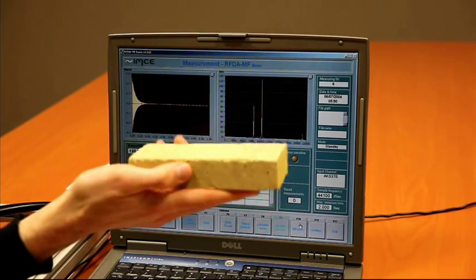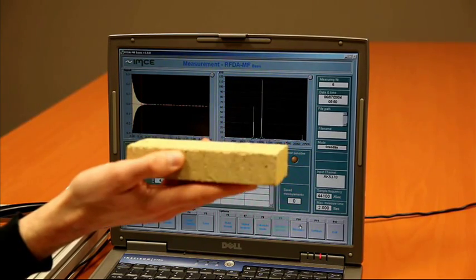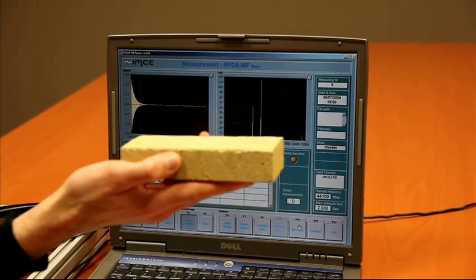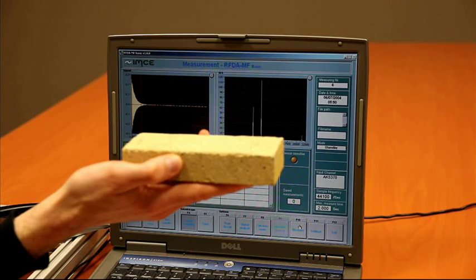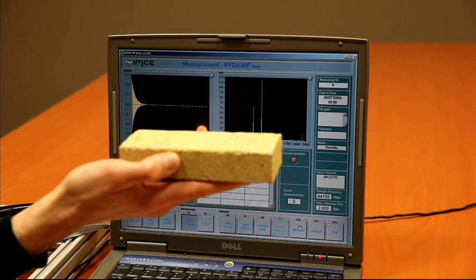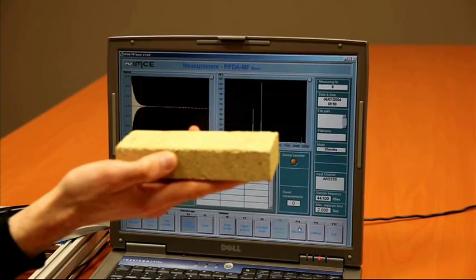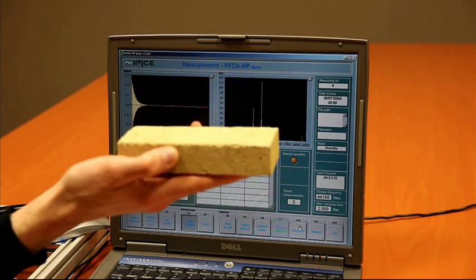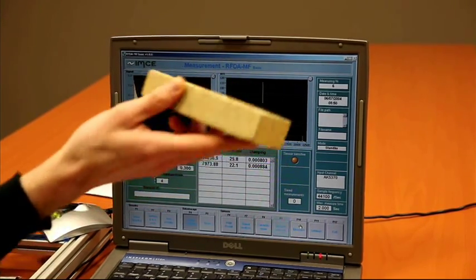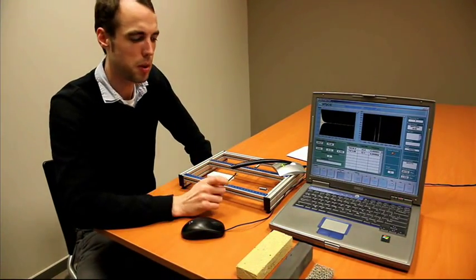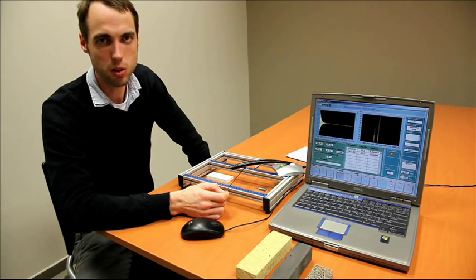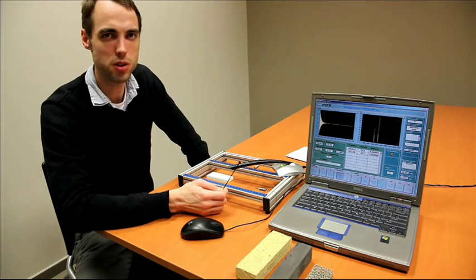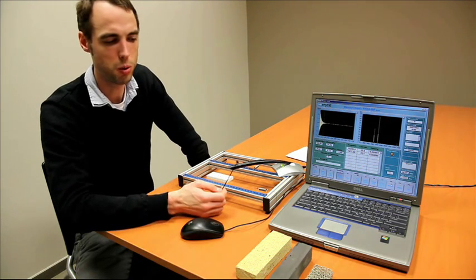We can also measure this type of material at high temperature. Then we use the same type of setup. Of course, we're going to use different materials in a more high temperature setup. And then we put the same setup inside of a furnace and perform measurements of the elastic properties and internal friction during heating and cooling. Normally, we measure the elastic properties every two minutes during heating and cooling. And this way, you can map out the elastic properties and internal friction of a material during heating and cooling.